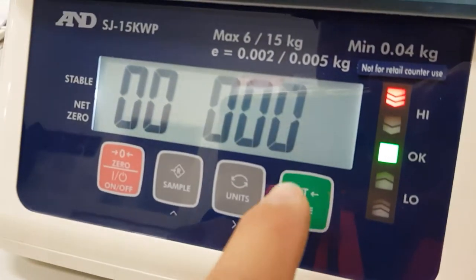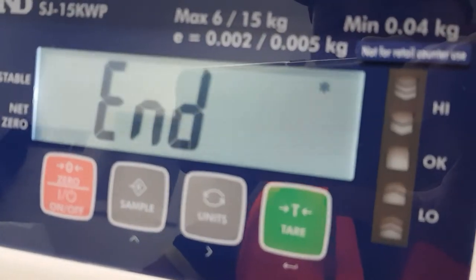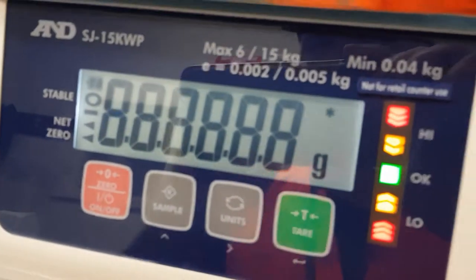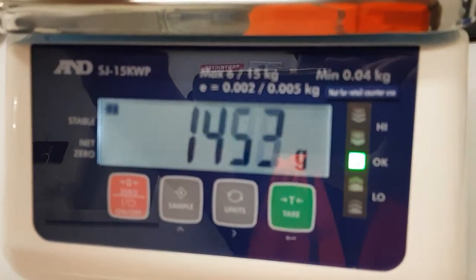That's now 2,000 grams. Hit enter, it says end, and it'll come back on in weighing mode. You'll see when I put some weight on the scale after it comes up with zero, the traffic lights will respond accordingly to the set points that we set before.